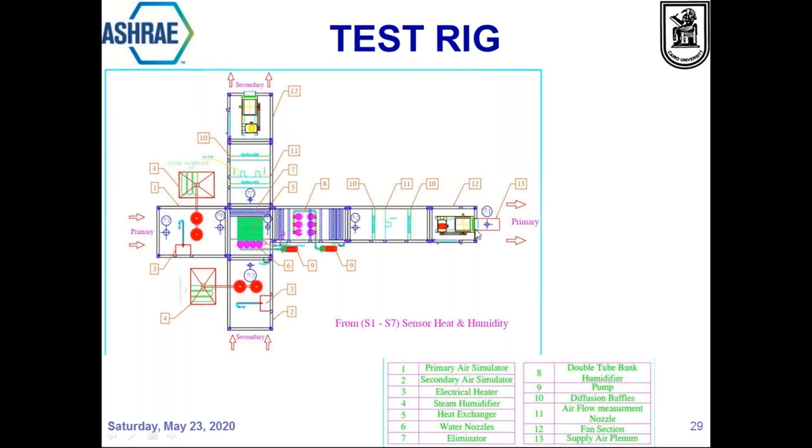And then we spray water and use a heat exchanger in order to cool down this air into conditions here. And then we compare the energy spent to cool down to the conventional method when we use mechanical refrigeration. In many cases, this type will not be enough, and we need additional mechanical ventilation, mechanical refrigeration. But at the end of the day, we are reducing the amount of energy we pay for, and life cycle cost analysis proved that this system will be very successful.